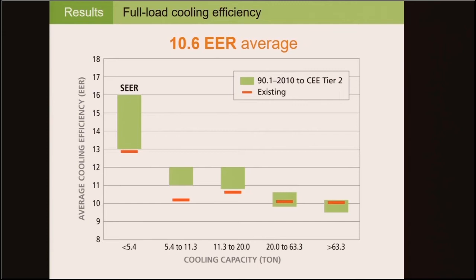The full load cooling efficiency is currently the major driver of how much electricity an RTU consumes. The average full load cooling efficiency of RTUs in Minnesota is 10.6 EER. There's a clear trend of increasing cooling efficiency in newer RTUs. In fact, over the last 20 years, the average cooling efficiency of RTUs has increased by 18%.